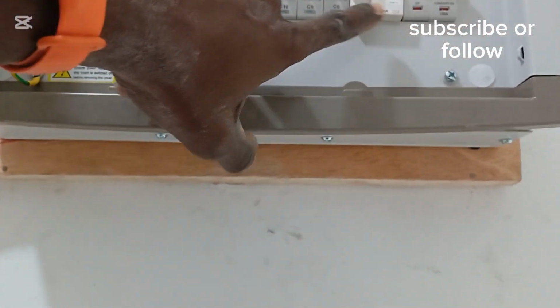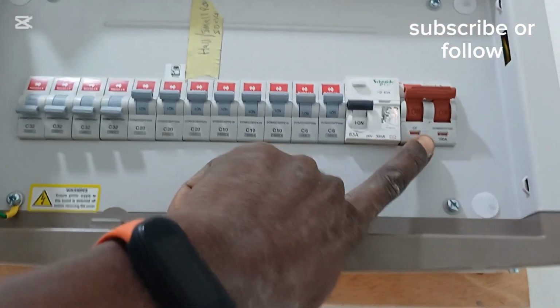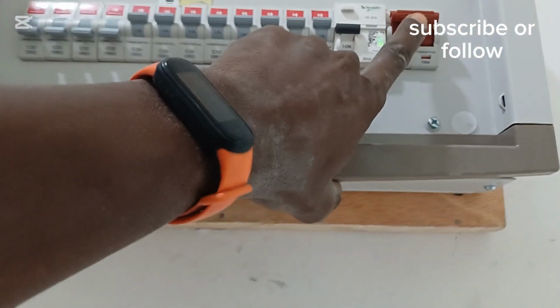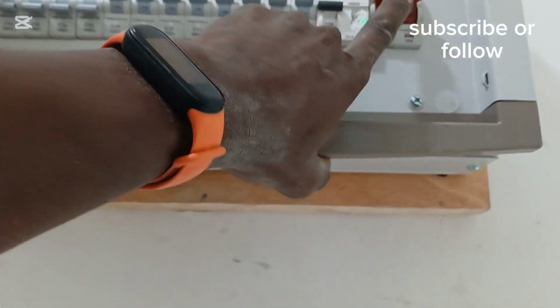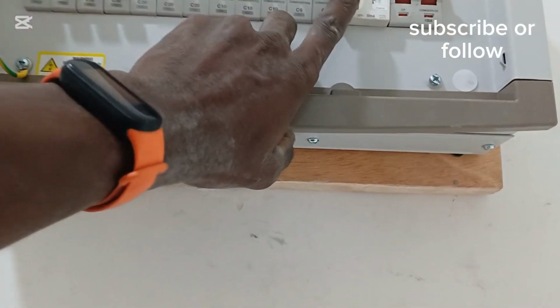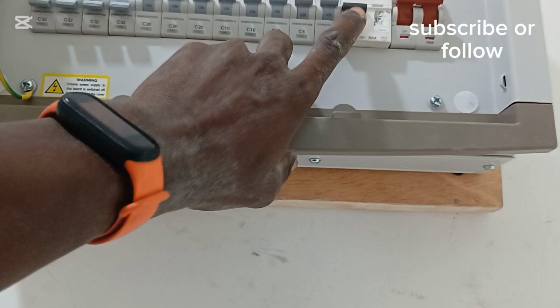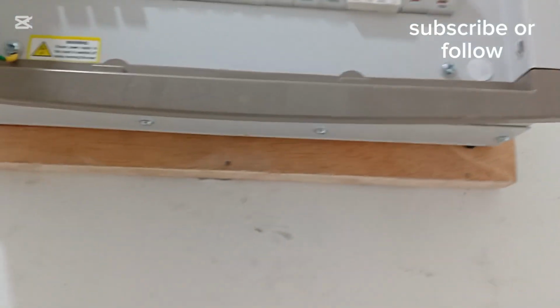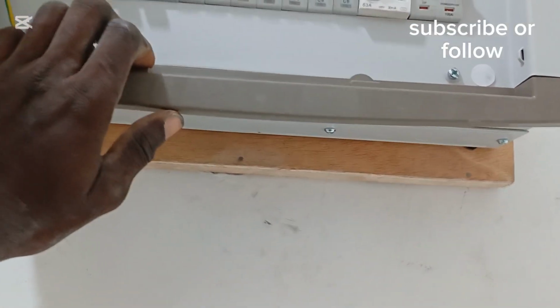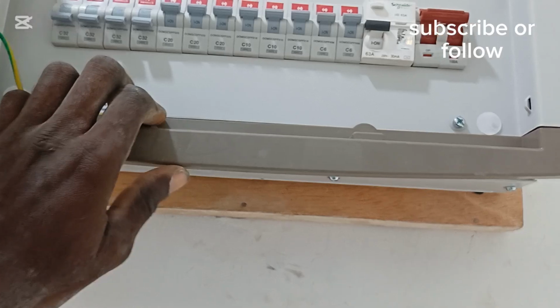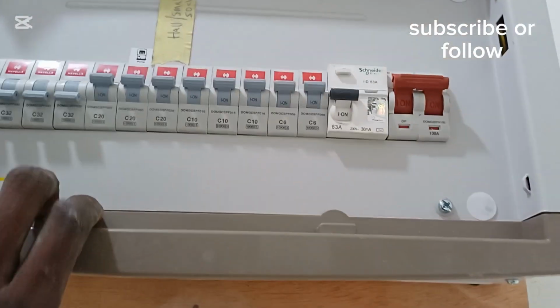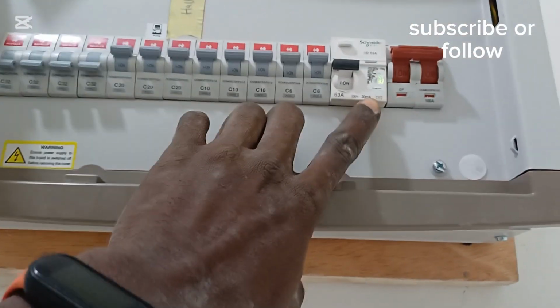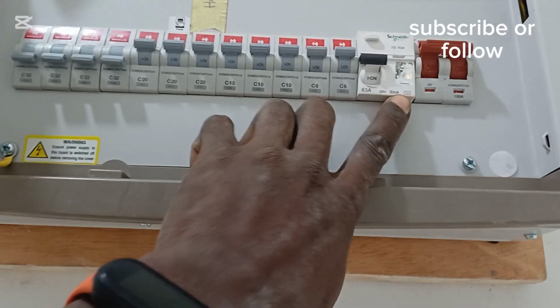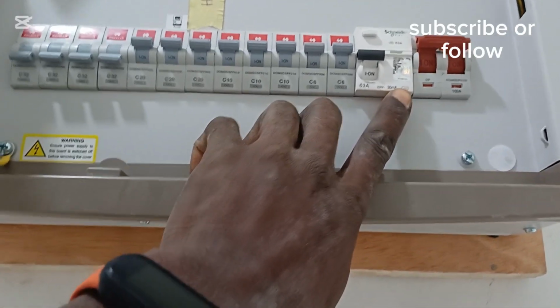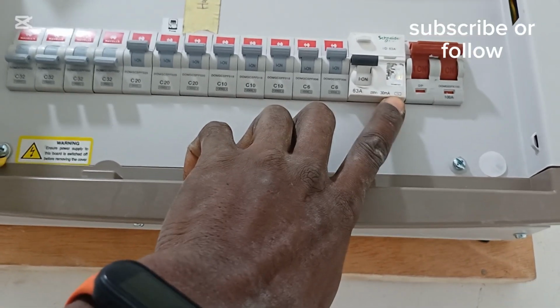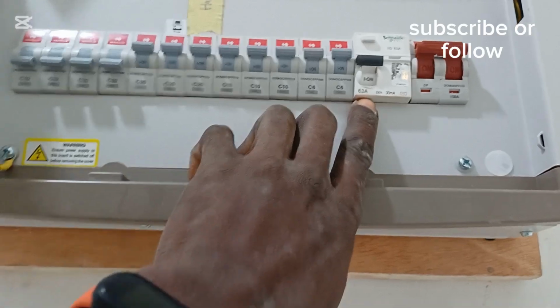When we tried to turn on, the MCB would turn on, but when you tried to turn on the RCD, it would trip. So I was thinking there was a contact between a live conductor and an earth conductor, because we all know as electricians that the RCD tackles earth faults.